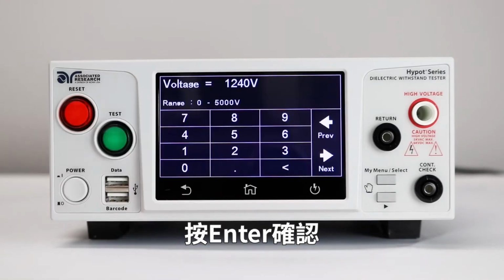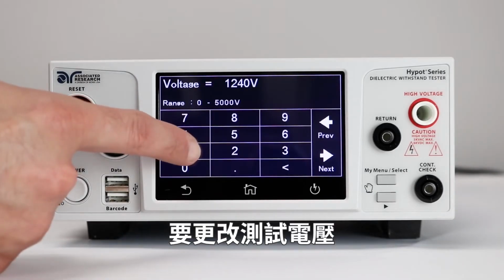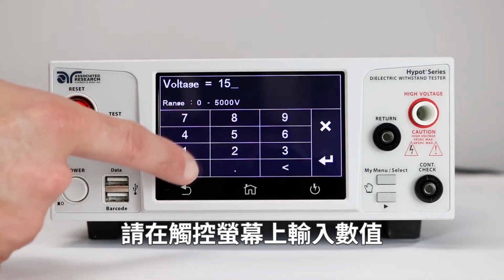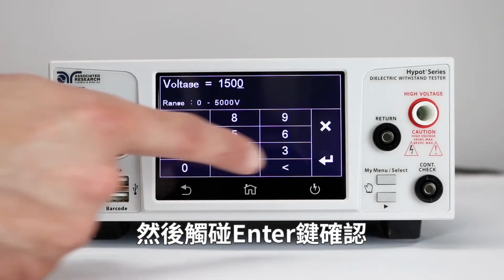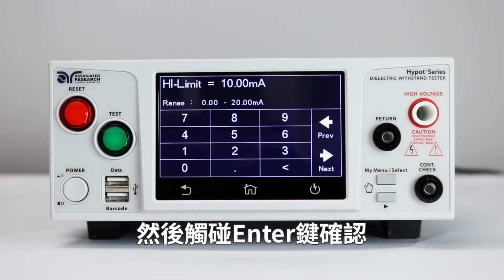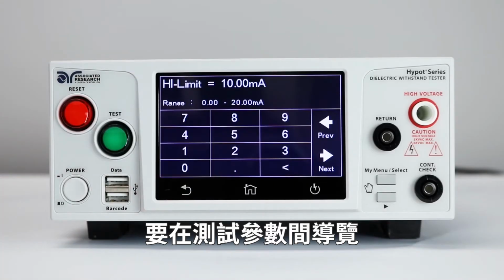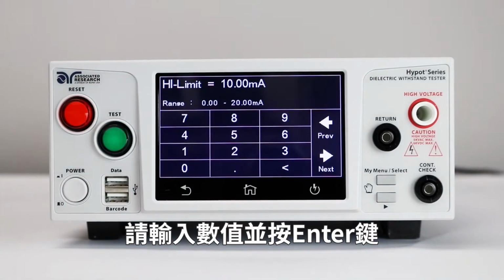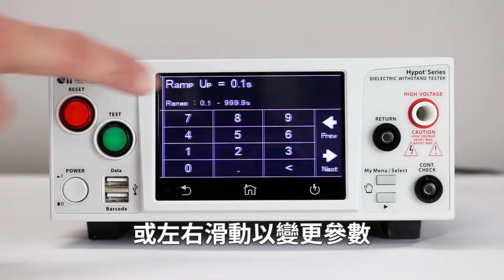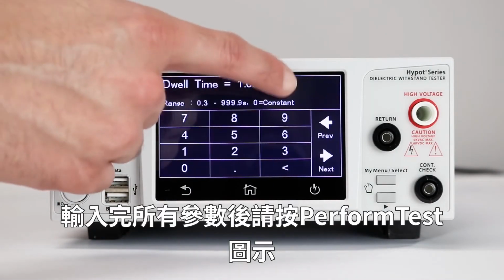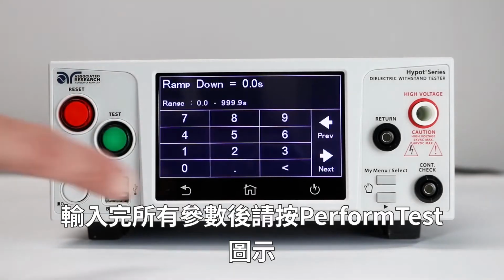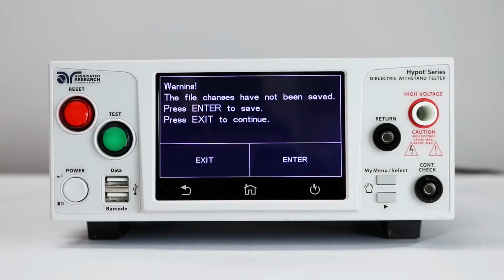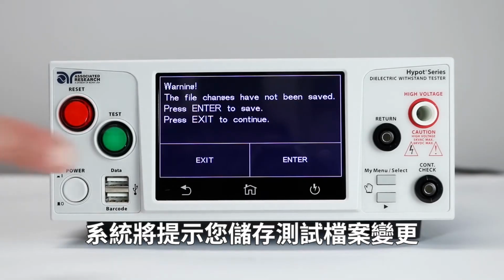Press Enter to confirm. To change the test voltage, input the numeric value on the touchscreen and touch the Enter key to confirm. To navigate between test parameters, either input the value and press the Enter key or swipe left and right to change parameters. Once all parameters have been inputted, press the Perform Test icon. You will be prompted to save your test file changes.